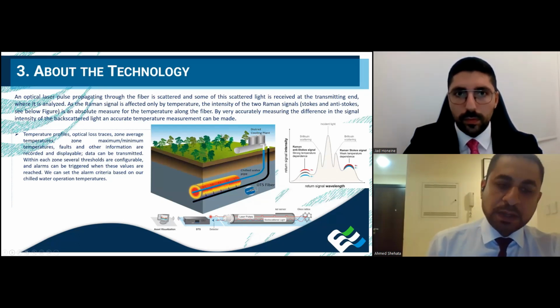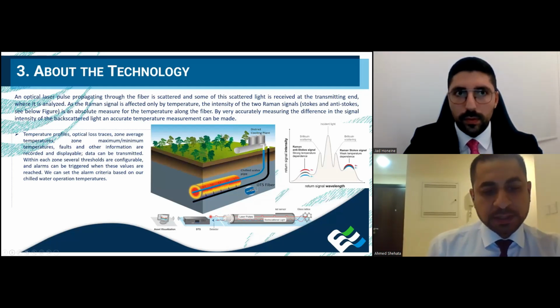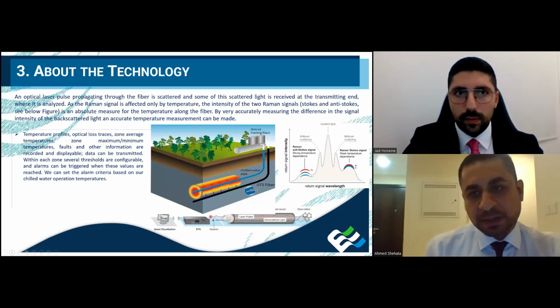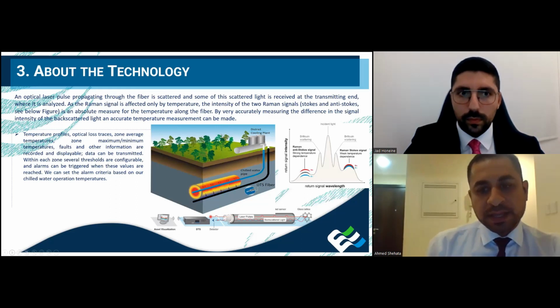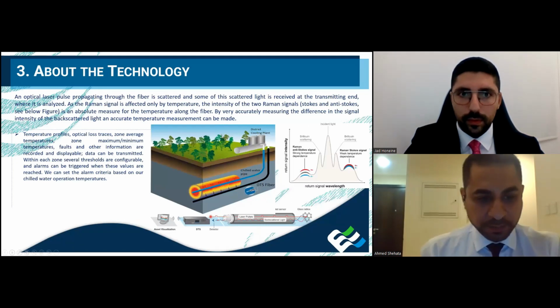But now we have an additional purpose for the fiber optic cable, in addition to remote control, monitoring, and remote reading of the meters. We use the fiber optic cable for leak detection, as a leak detection sensor, to detect and determine the location of the leak along the chilled water pipe.